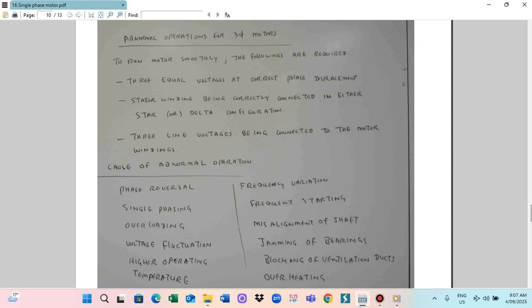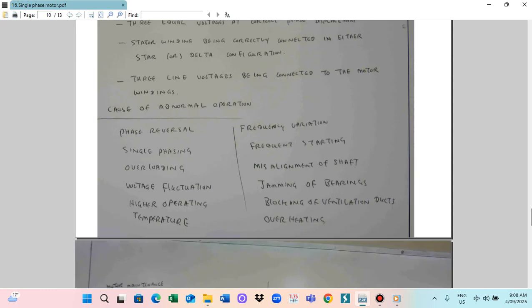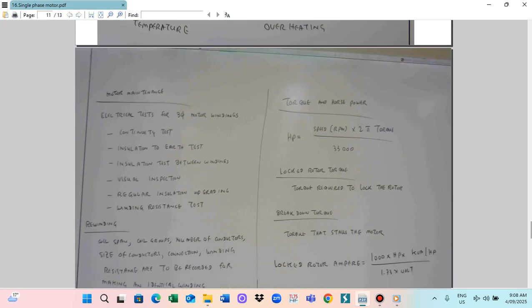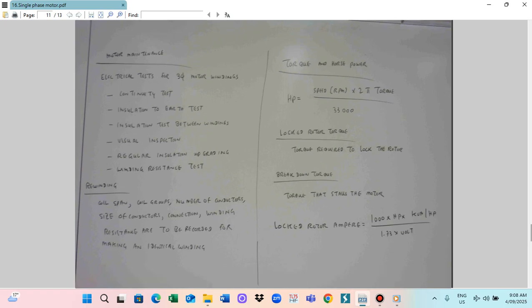So in this case, you have to check the motor. Usually it is maintenance. Maintenance means you have to do a continuity test. Continuity test means you test from the motor winding. All three-phase windings must have the same resistance. So we have to do the continuity test. Another one, we also have to do the insulation resistance test. In this case, you have to use the megger. The megger measures the insulation resistance between the motor winding and the terminals, which has to be done. And also the insulation test between the windings.